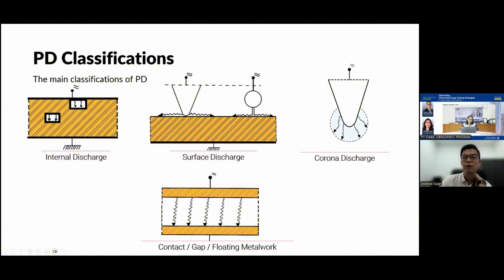Number three is corona discharge. Corona discharge is actually a discharge from a sharp angle. If it's discharged to the air, it's harmless, but if it discharges to a surface, it may cause problems. This is very common in open switchyards - sometimes when you walk across one you hear a loud crackling sound. A lot of the time that's corona discharge going through the air, and once the energy bursts through the air, sound energy is generated, so you hear the crackling. But if it's discharging to the air, it's not a cause of concern. If it's actually pointing to another area or switchgear, that may cause problems later.